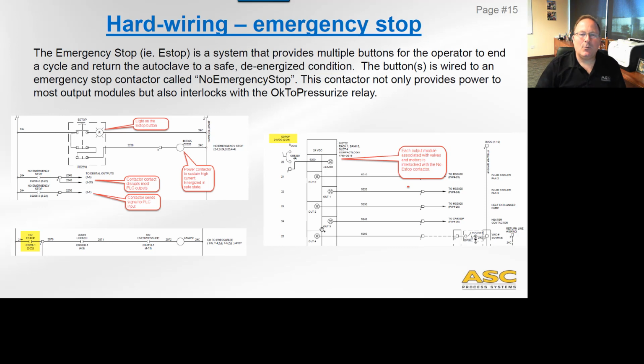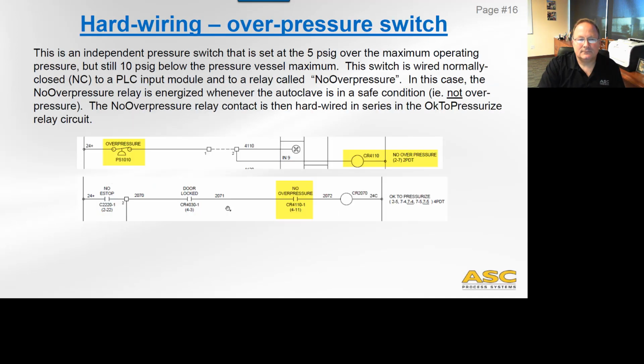So the only outputs that remain on are the things that are on lights, alarm lights, for example. We're not going to e-stop an alarm light, and indication things like horns and that type of thing. But all other outputs, any valves or any motors, those are all going to be interlocked. Okay, and we also see that the no e-stop is also in the OK to pressurize relay, which makes it part of the permissive for auto enable as well.